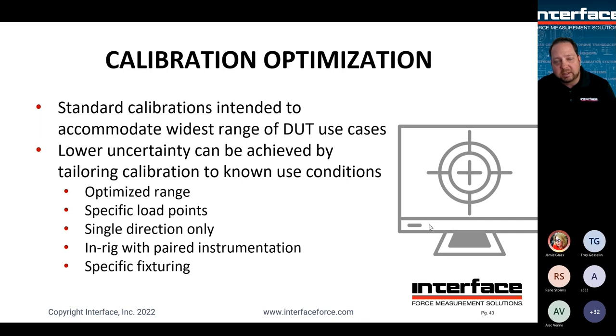And what that's going to do is basically take potentially uncertainty out of the equation for the system level, or from the instrumentation, from the cabling. And then you're looking at what's the total uncertainty on just the calibration itself, because at that point you're delivering system level measurement output against a very specific calibration load point, right? So at that point, if you can correlate that data back to what the actual test is that you're trying to do, you'll be able to take a lot of that uncertainty out of that error budget, right?